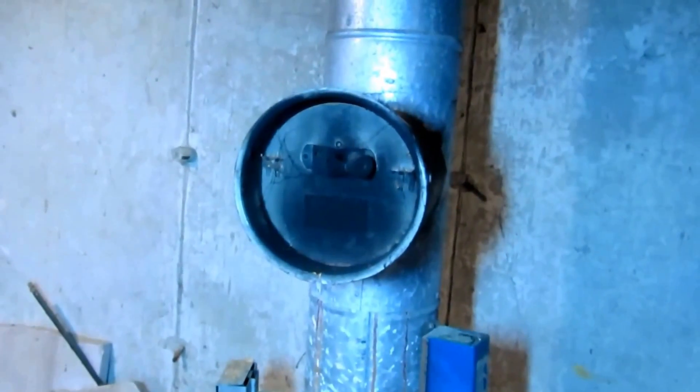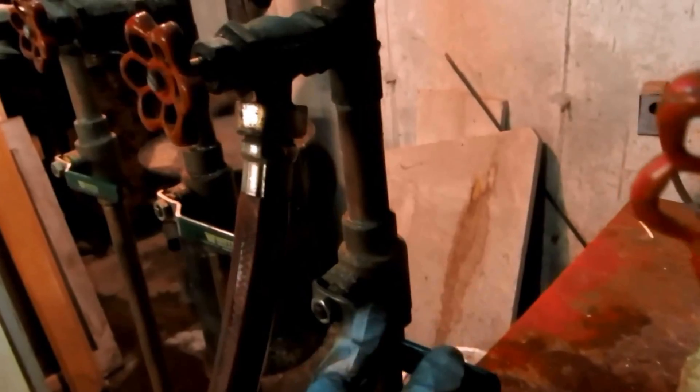Looks a little black there — that ain't good. Sending the water up the supply, I got those zone valves opened. Coming back to return — can't go back because the ball valves are off and it goes out the hose, purging out the air.